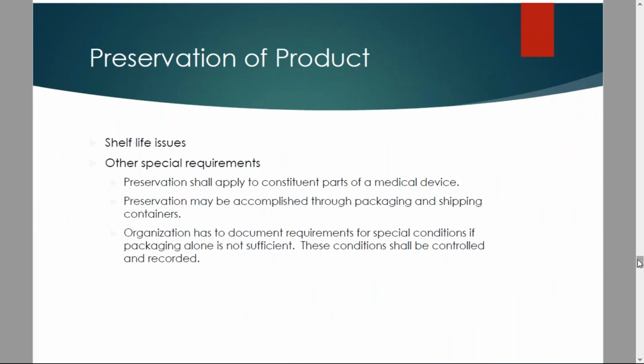We'll also see nonconformities related to shelf life. So we need to make sure that their stock rotation is appropriate. Product that's expired is appropriately removed, so it can't be shipped to a customer. It can't be incorporated into the manufacturing process. Preservation requirements may apply to constituent parts of a medical device and not just the finished device. Auditors and clients need to be aware that preservation can be accomplished through packaging and shipping containers. So is the packaging and shipping appropriate to the type of device that's being sent out? And an organization has to document requirements for any special conditions if packaging alone is not sufficient. And these conditions shall be controlled and recorded to ensure that they're consistently met.